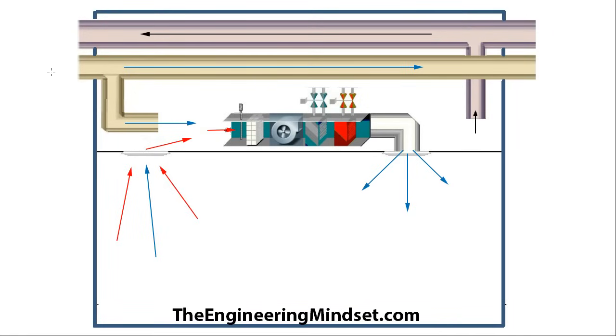The fresh air comes in through the supply duct and enters the space above the false ceiling — into the void above. It enters the fan coil unit, passes through the fan and filter, and once treated to the required temperature it's pushed out through the diffusers into the space. This pushes the used air in the room up through the return grill and back into the ceiling void, where it's mixed again with fresh air. Some of that return air in the void is sucked out by a duct and pushed back out to atmosphere.